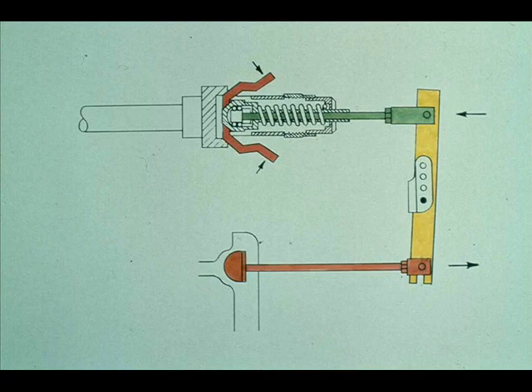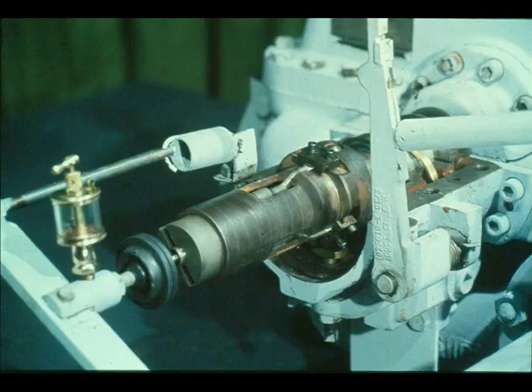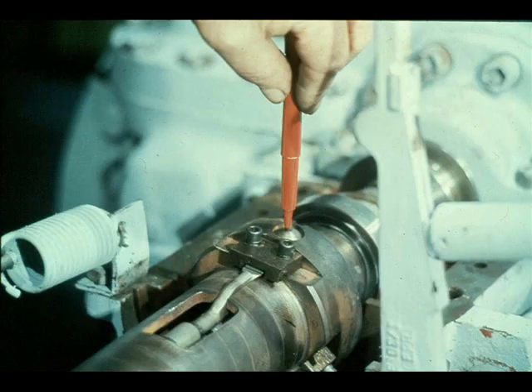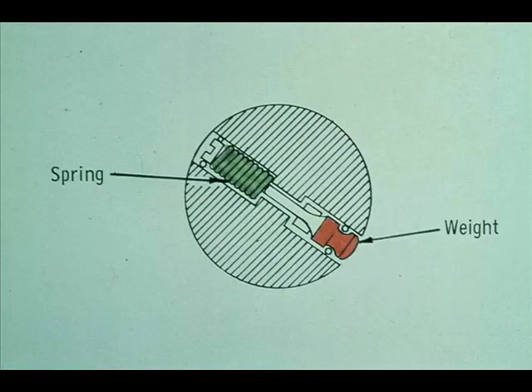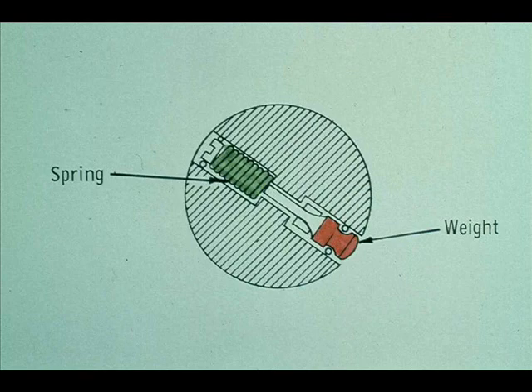That's the basic idea of the principles of operation of a mechanical shaft constant speed governor. You are not expected to become an expert, but these illustrations should serve as a guide to understanding the basic principles. The final mechanism to become familiar with is the overspeed trip, designed to stop the turbine if the constant speed governor should fail. This device is extremely important, since a steam turbine will run wild and blow up in seconds if not controlled or shut off. A very important part of the overspeed trip mechanism is the trip pin, located in the governor case fastened securely to the turbine shaft — a pin that extends through the shaft and is weighted on one end, restrained by a spring on the opposite end.